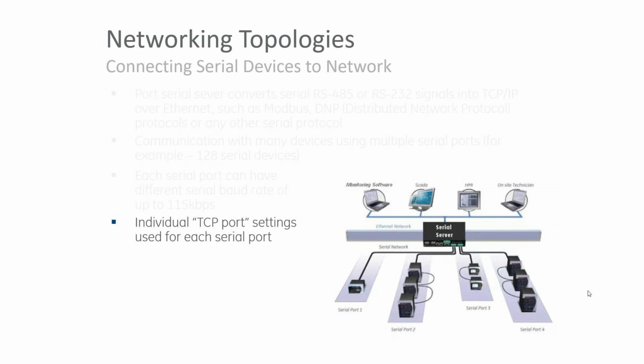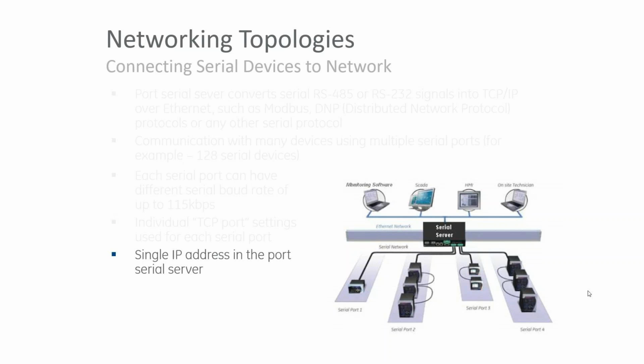And that's where the port settings come in to say, hey, where I need to communicate to the different devices, I might have different ports with different devices, different addresses to the different devices. I can connect to the serial server with one IP, but then I tell the serial server, this is the port I want to connect to, or this is the address that I need to connect to get down to the individual device. So you just need to connect to that one port on the serial device with one IP address, but you need to identify which device you need to talk to.